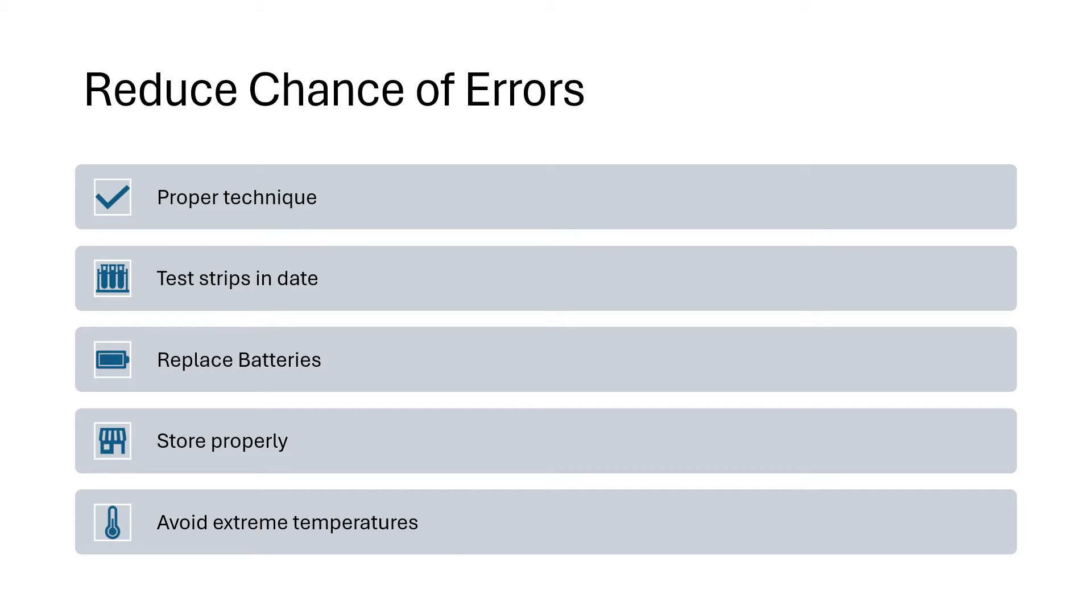Replace the batteries if you're getting frequent error messages. If you haven't replaced the batteries in a while, sometimes low batteries can cause error codes to occur. Always store the test strips properly. Ensure that you close the lid and keep them out of extreme heat and humidity, and avoid extreme temperatures.